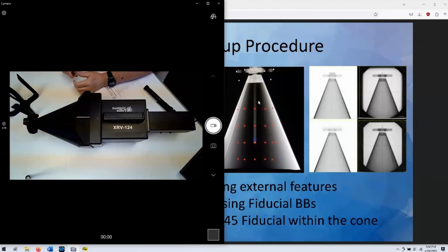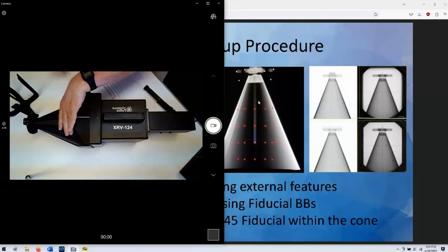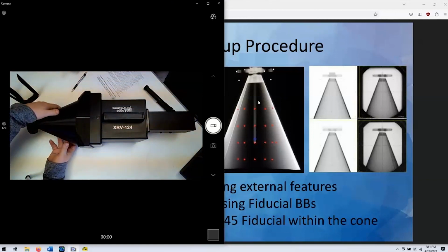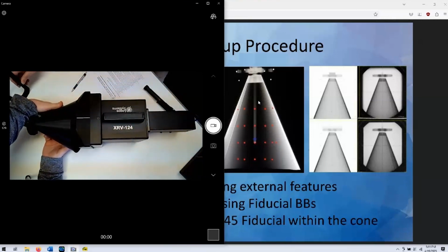The black plastic shroud that covers the imaging cone is 0.8 millimeters thick and does not substantially affect the measured size, shape, or position of the proton or X-ray treatment beam. The purpose of the shroud is to prevent ambient light or laser light in the treatment room from illuminating the calibration reference holes on the imaging cone. The shroud can be easily lifted off the cone by first removing the tape that holds the ends together.